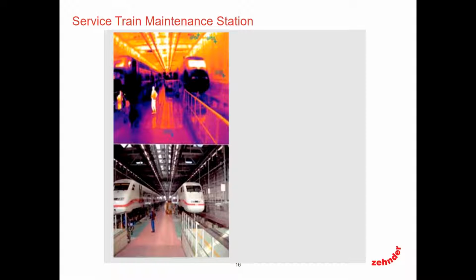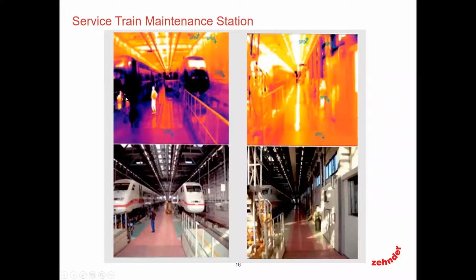And what do we do as designers now? We have to figure out a solution to get that hot air down to the lower area where all those occupants are and where they're working. On the other side of the building, on the other side of the wall, excuse me, we did a radiant system. You can see in heating mode how all those objects in the space absorb the energy and then emit it back into the space.